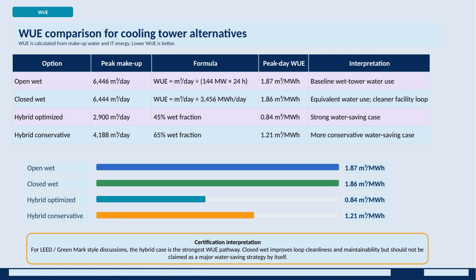The hybrid conservative option uses more water than the optimized version at 4,188 cubic meters per day, yielding a WUE of 1.21. This approach offers a moderate water-saving benefit, balancing efficiency with operational conservatism. For certifications like LEED or Green Mark, the hybrid systems, especially the optimized one, are the strongest pathways to reduce water use effectively. While the closed wet system enhances cleanliness and maintainability, it shouldn't be considered a major water-saving strategy on its own. Overall, choosing the right cooling tower setup can make a substantial impact on both water consumption and facility performance.